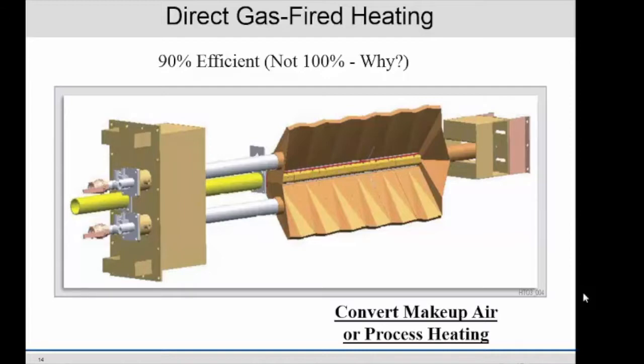And some people think that because you're burning the gas and dumping everything in the building, that's a problem. It's not a problem. Okay, only in buildings like sleeping quarters you wouldn't do that, because these buildings are going to have ventilation, enough ventilation to handle the CO2 that is in the burned gas. So it's very common to do direct gas fired in a building, open bay type buildings.